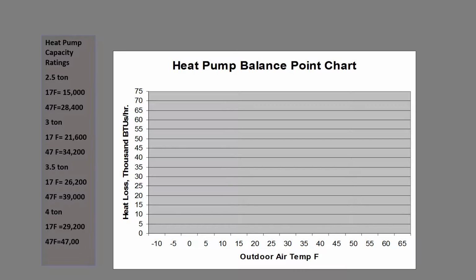So this is how to create a heat pump balance point chart. The first thing that you do is you create the heat loss of this house. You need 1 point to do that. You can take your heat loss at any given outdoor temperature. Usually it's your design temperature, and you anchor it over to 65 degrees. Sure enough, the warmer it is, the less the house needs to maintain temperature.